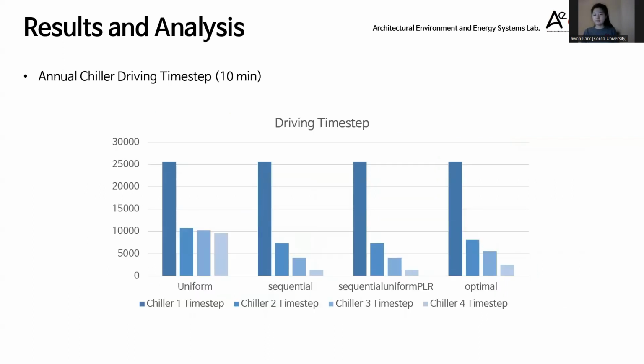The following analysis pertains to the operating hours of each chiller. As the simulation was designed to calculate the cooling load in 10-minute intervals, one time step represents 10 minutes. Although the total cooling load remains the same for all algorithms, the uniform algorithm has longer operating hours for chillers 2, 3, and 4 compared to other algorithms. Therefore, it can be inferred that the uniform algorithm operates at lower PLR compared to other algorithms. The optimal algorithm also showed longer annual operating hours for chillers 3 and 4 compared to the other two algorithms.